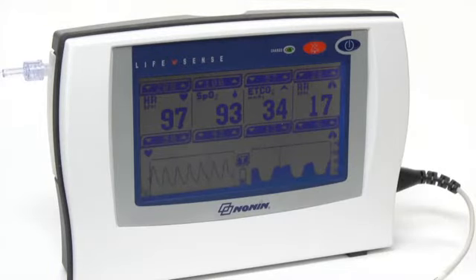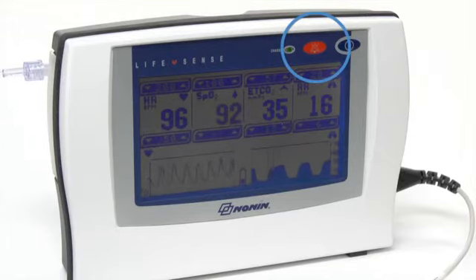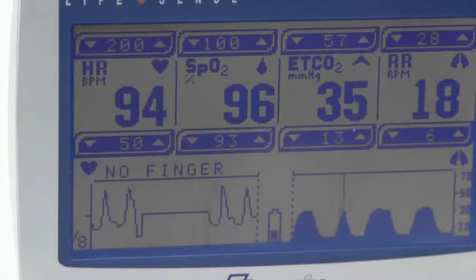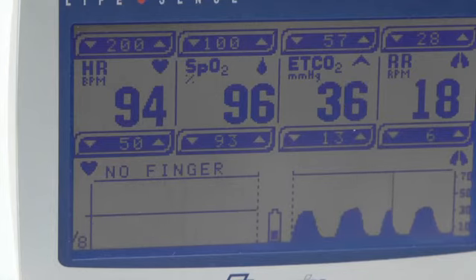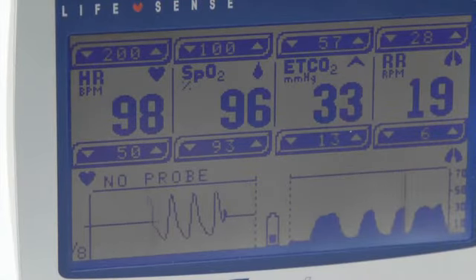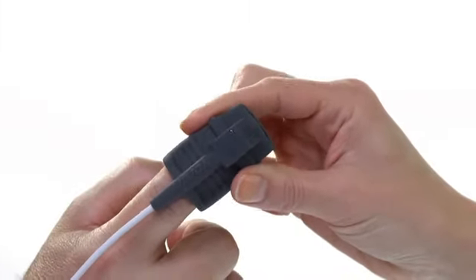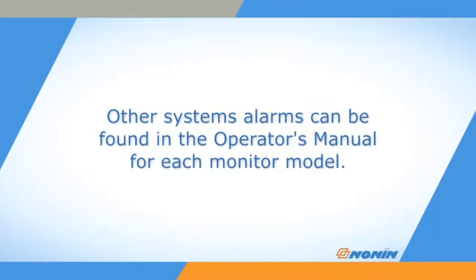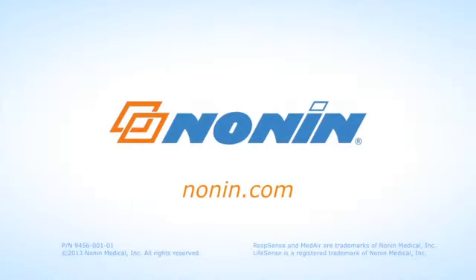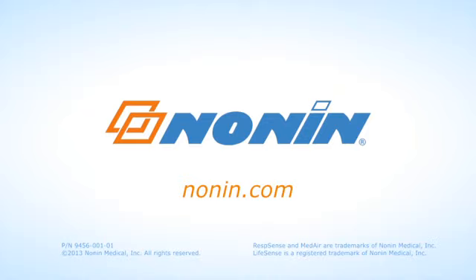SpO2 and pulse rate monitoring will generate an alarm if the readings fall outside of the default or preset limits. The audible alarm can be silenced with the Audible Alarm Pause/Resume button. The alarm will clear when the readings return to the limits on the monitor. Sensor signal strength alarms may occur if a problem is detected. If an alarm occurs displaying no probe, no finger, artifact, or signal low, check the position of the sensor on the patient and the connection of the cable to the monitor. Other system alarms can be found in the operator's manual for each monitor model. You can find additional use information on this and other NONIN products at www.nonin.com.